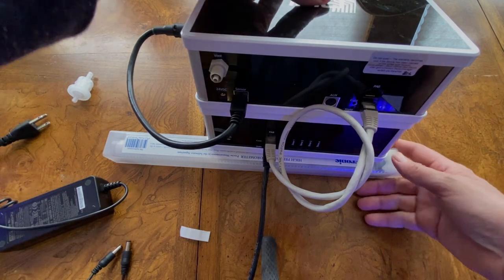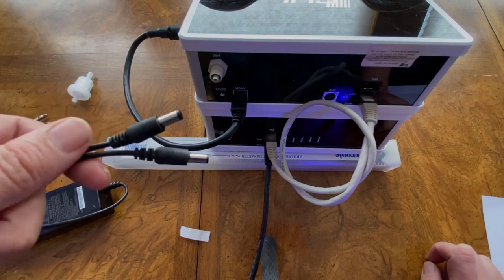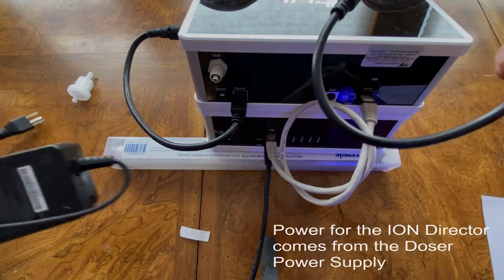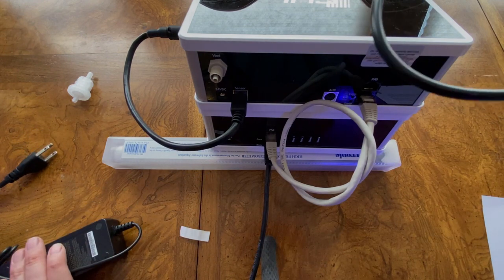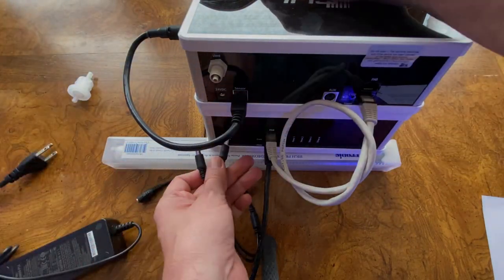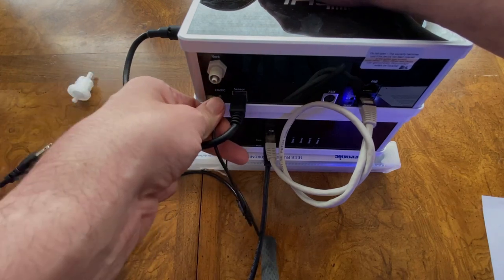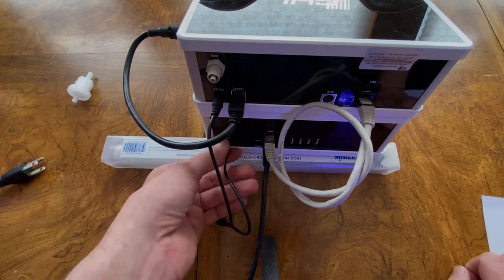Next, install the power cables. You'll receive a Y cable with your Ion Director order. This Y cable allows the Ion Director to share the same power supply as the doser, eliminating the need for an additional power supply in the cabinet. Plug one side of the Y connection into the doser and the other into the Ion Director.